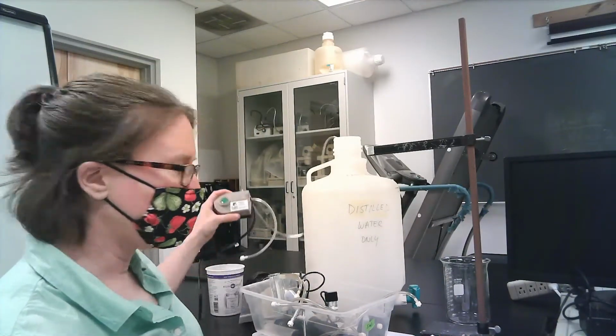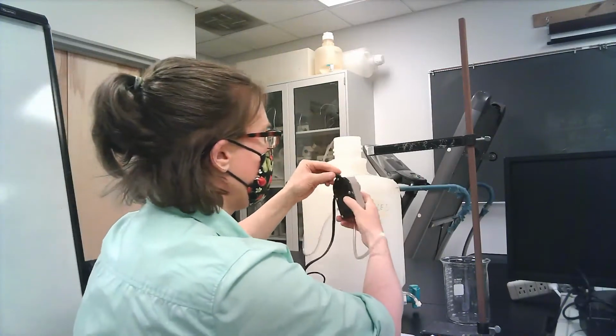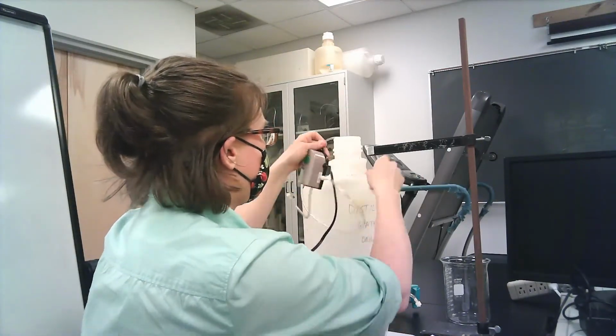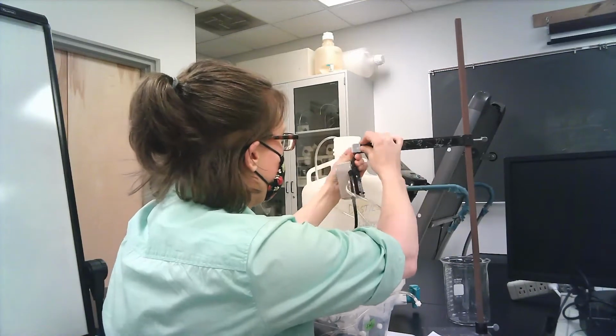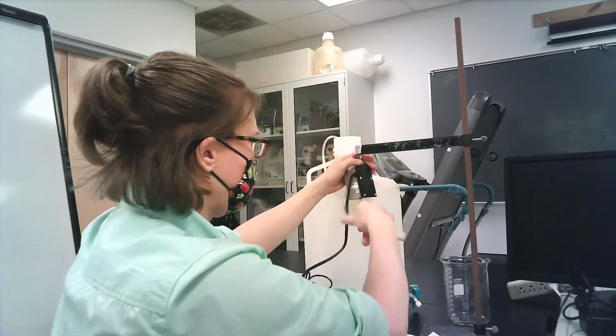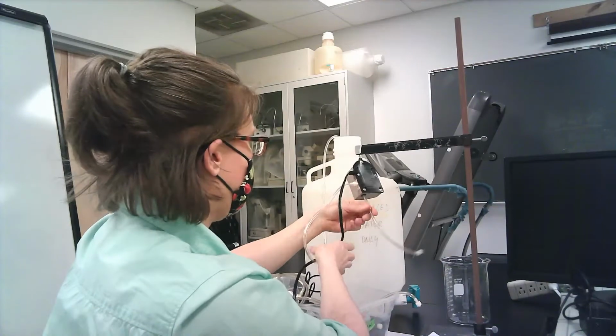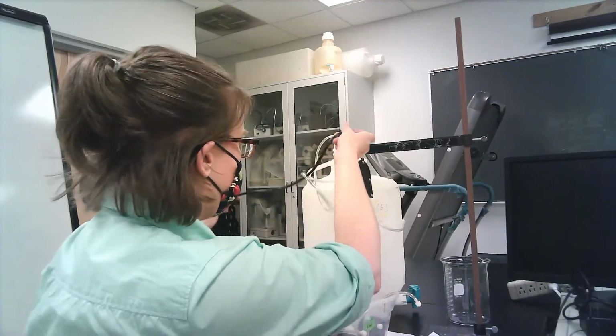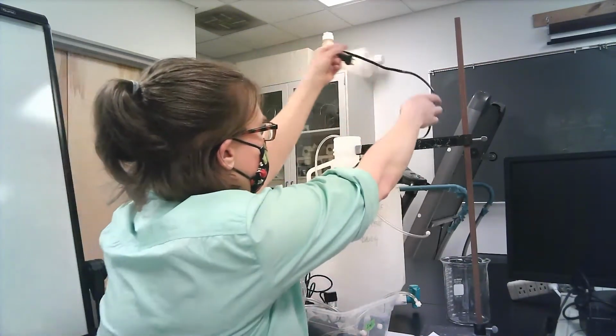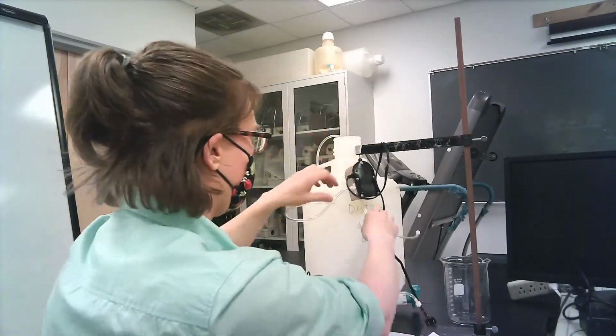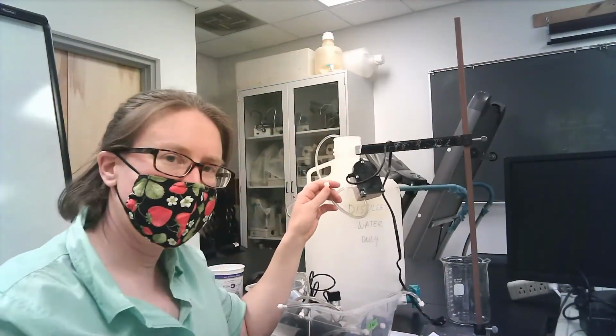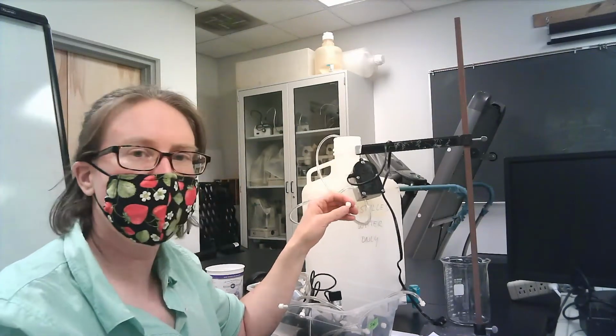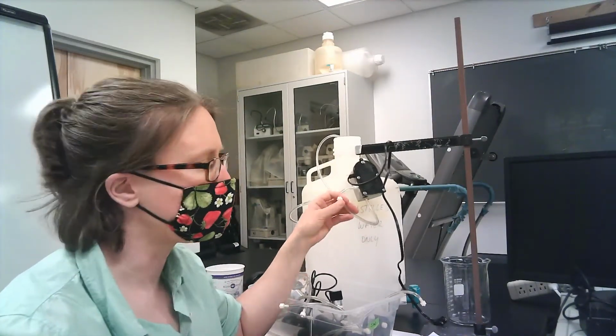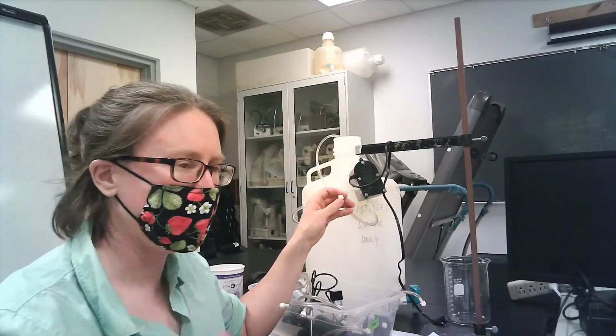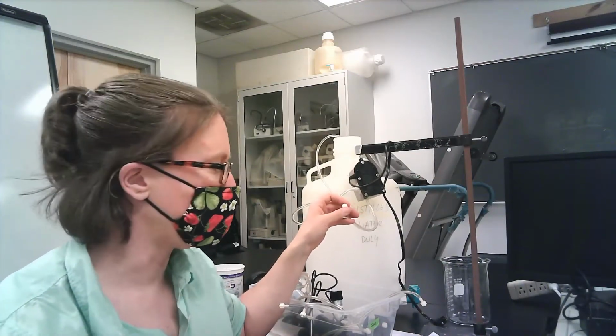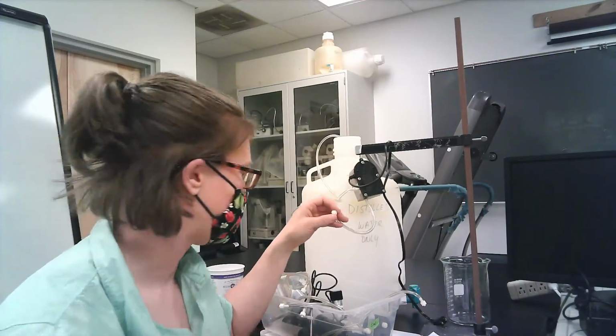After we've got our gas pump connected in, and if you would like, this ring stand here has some attachment points to keep everything organized. We're going to pump air through this gas pump, and we'll need to connect that up to the power supply in a little bit. From there, the next thing we want to do is remove water that's in this air, because the relative humidity can have a dramatic impact on the precision of the oxygen measurements that we get.